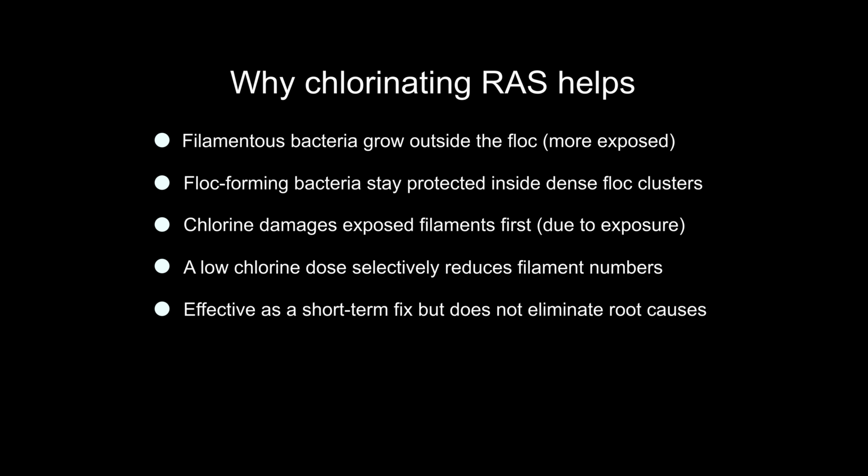But if you stop the chlorine without fixing the underlying problem, those filaments will come back and keep causing problems. To truly solve the problem, you need to figure out what caused the filamentous bacteria to take over. It could be an internal process issue, like the dissolved oxygen being too low or the food to microorganism ratio being off. Or it could be coming from outside of your system, from an industrial discharger sending a slug of grease or high sugar waste.